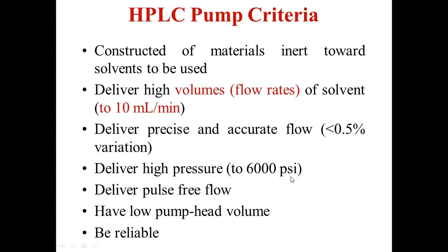At least 6,000 psi pressure must be able to be created. Pulse-free flow must be obtained. If pulses are obtained, they are going to damage the separation process. And the pump must have a low pump head volume, because we will be using a very small volume of the sample solution, and even the mobile phase will be used with a limited volume. Therefore, the pump head volume should be very small. It should be reliable. So accuracy, reproducibility, selectivity, everything must be considered while choosing the pump.